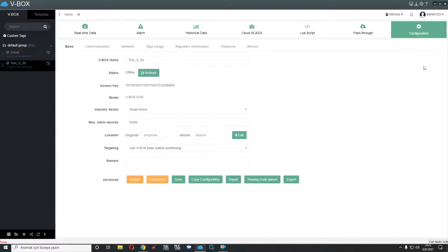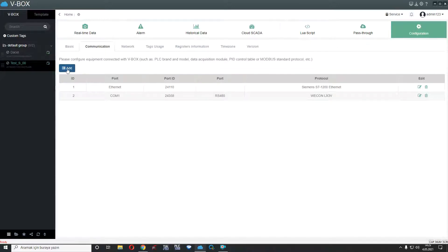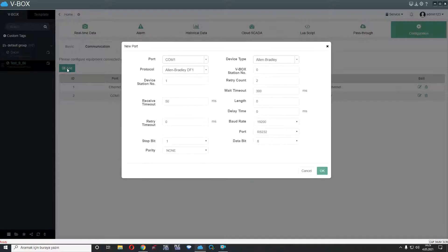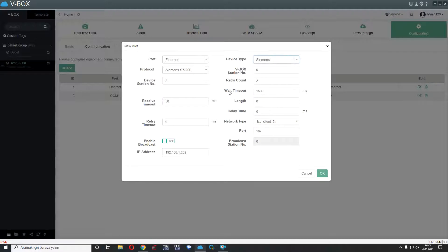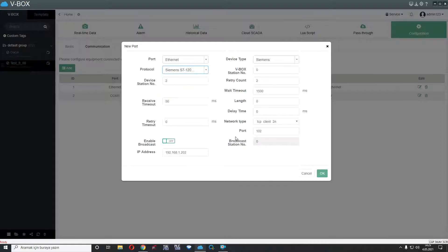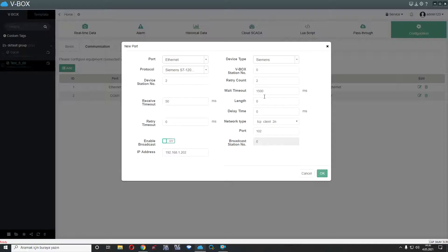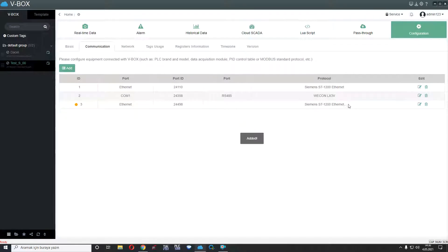First of all, if you communicate with PLC or any devices, you have to select communication part and add any device. For example, I will add from Ethernet and Siemens PLC, S7. Here is some settings for connection to any device, for example, PLC's IP, PLC's port, network type, delay time, wait timeout, etc. And if I click OK, you can see I added a new device here.